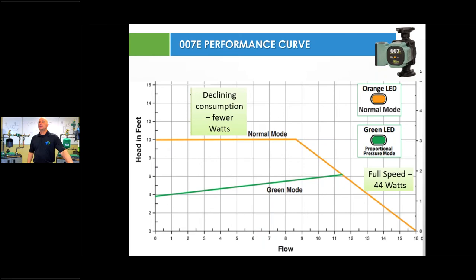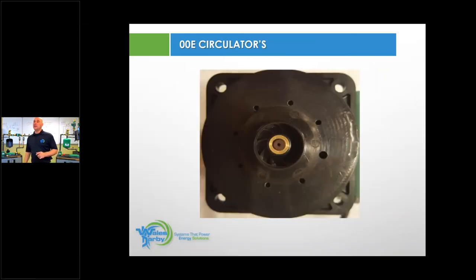This is a typical 007E curve. So it will run at 10 feet of head all the way out till we get to about 8.25 gallons per minute, so about 82,500 BTU, and then it will start to run along its slanted curve. And basically what we're looking at when we're running on this curve is about 44 watts. When we're running along this curve right here, the 10-foot curve, it will be less, and it's going to be less based upon how many holes or zone valves are open within the system, or if it's just a circulator system, wherever the gallon per minute rate flows. So 4 gallons a minute and 3/4 pipe, it would run right here, and it would reduce the power demand of that circulator. So next slide up is a 007E, and this is basically what we're looking at.